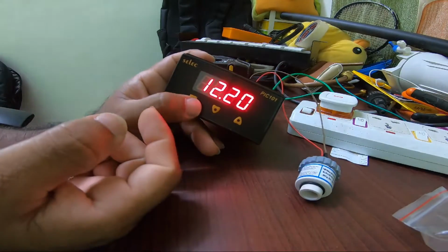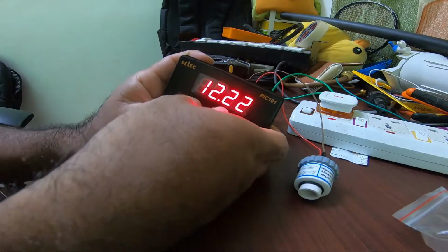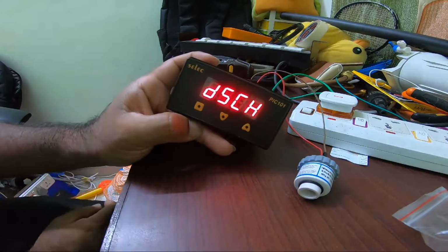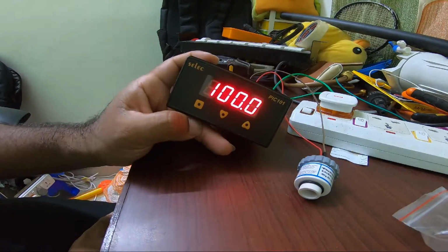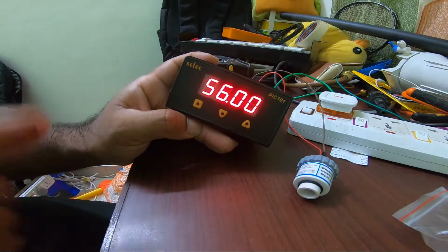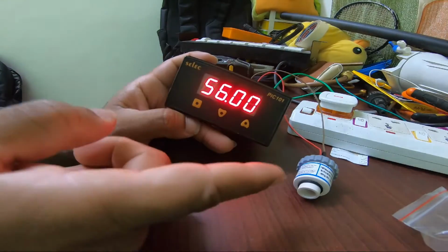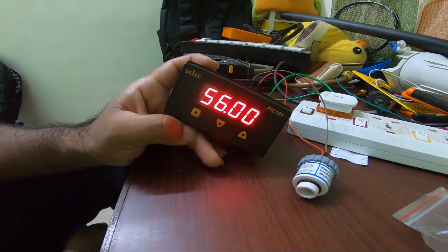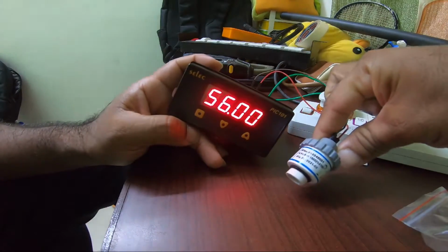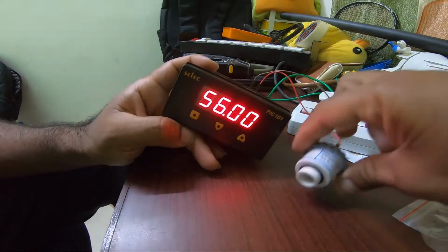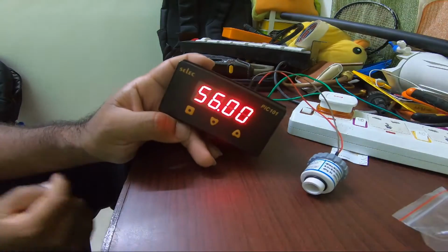In order to change, just press the square button and the upward or the downward button to change the values. Okay, after this, press the up arrow. This is a descending value. What is the maximum it should show is 100. When it should show 100 is here, 56. When it goes to 56 millivolt, that means it is measuring 100% pure oxygen according to my oxygen sensor. Normally it will go around 55 to 60 depending on what sensor you use. My sensor model reaches 100 at 56.